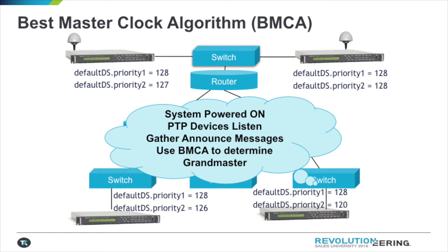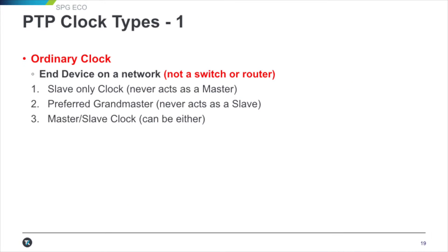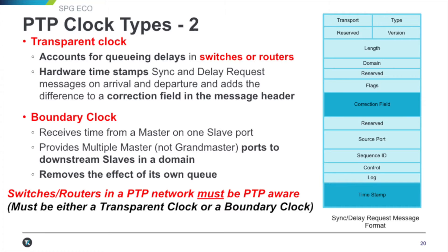When the system is powered on, the devices listen to gather announce messages and use the best master clock algorithm to determine the grandmaster. Ordinary clocks are devices that are not a switch or a router — they could be a slave, a master, or either, but they are not a switch or router.